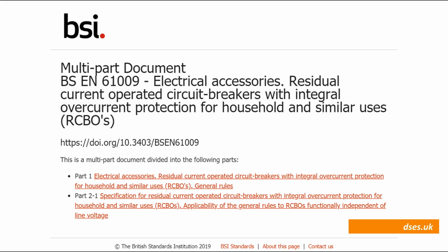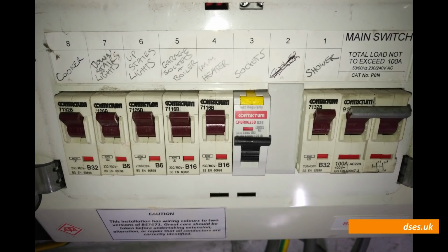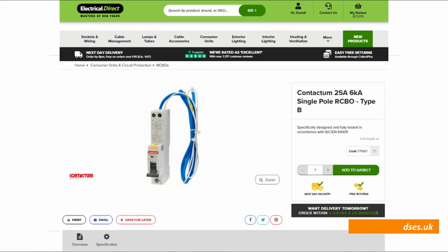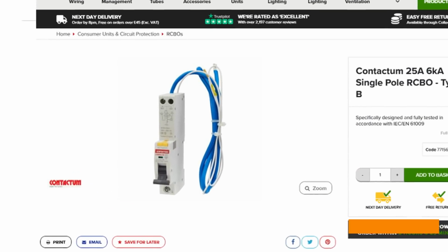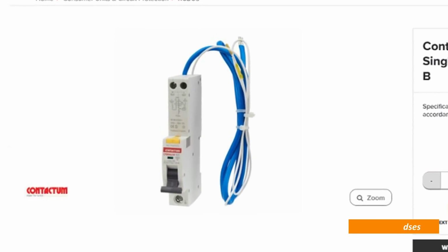So the fact that the socket circuit was spliced into this device means it lacked suitable overcurrent protection and was only protected by the main fuse at the cutout. A situation fairly rapidly remedied thanks to the good folks at Electrical Direct and their ability to supply me with the correct Contactum device for that circuit in a short space of time.